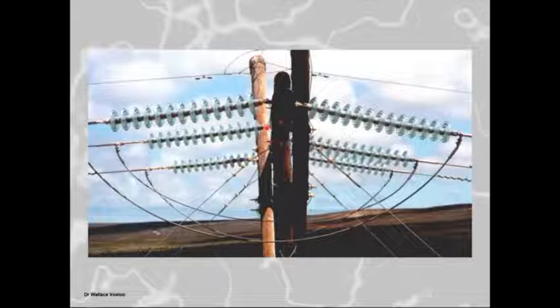Now, unfortunately, most people in the world don't understand high voltage engineering so well, and also don't really have an idea of what influence different aspects in the gap have on its breakdown capability. When an air gap has moisture in it, it's actually more difficult to break down than a gap without moisture. The reason is that these large water molecules in the gap prevent the little avalanches from forming and absorb the electrons, which results in a higher breakdown voltage being required for that gap, instead of a lower one. So moisture in the air gap actually helps the gap not to break down. It's quite an interesting one once you start understanding the breakdown mechanisms.